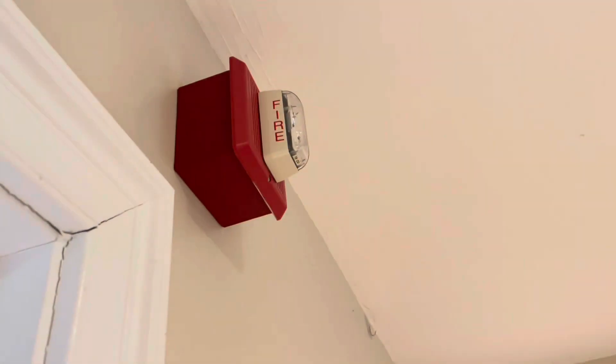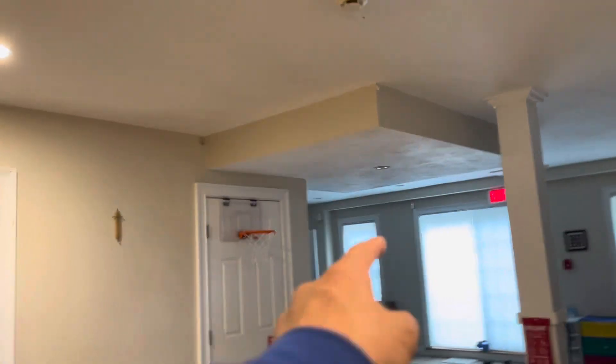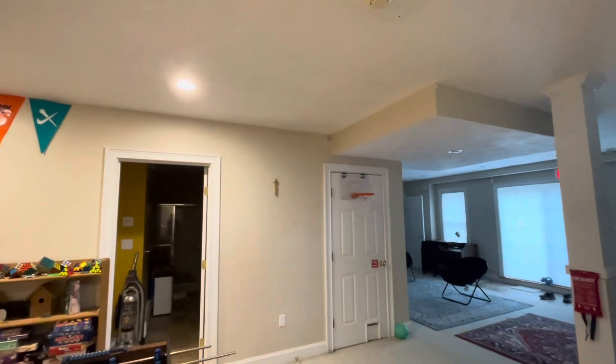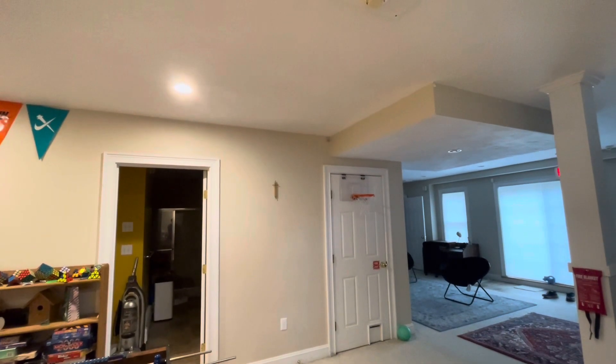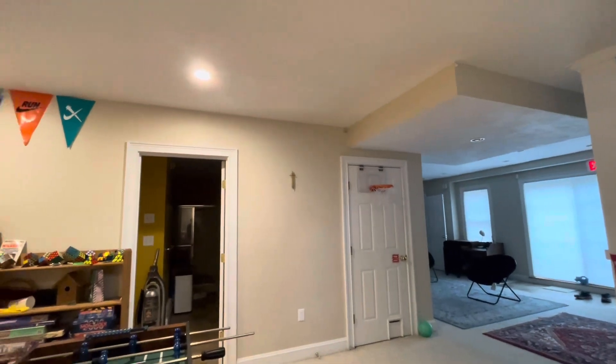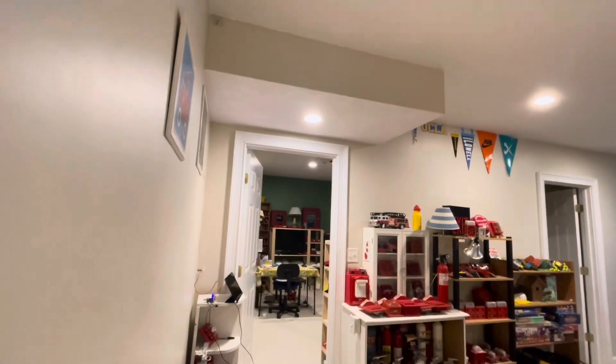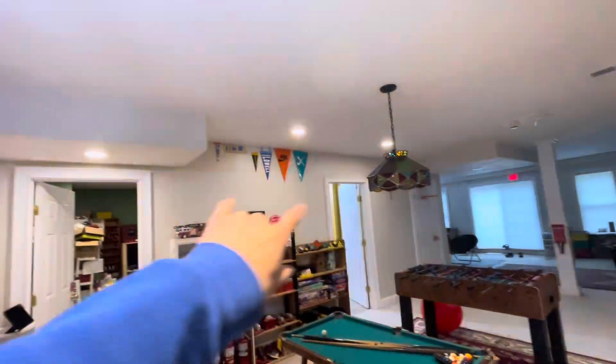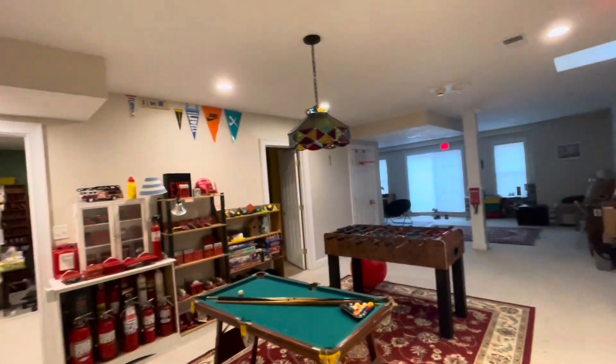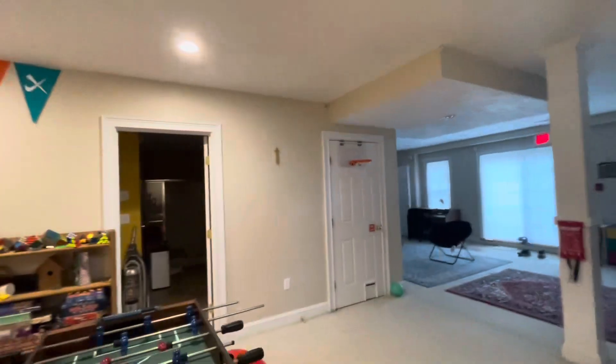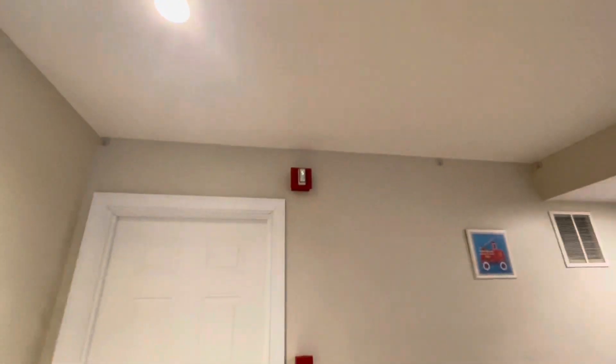Something interesting is the unenhanced devices actually do sync with each other. It's actually kind of crazy. All these devices here are technically non-syncable, but they all do sync. The camera will pick up their flash. I mean that's a little odd. The actual enhanced devices that are supposed to sync, like the one in that room and this one here, sync. So basically we have two different sync patterns, which is technically code compliant. I'm not sure how they're synchronizing because they're not supposed to be syncing, but that's that. Thank you for watching, please do like, comment, and subscribe, and I'll see you in the next one.